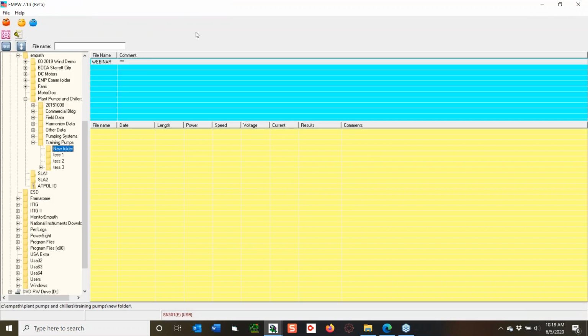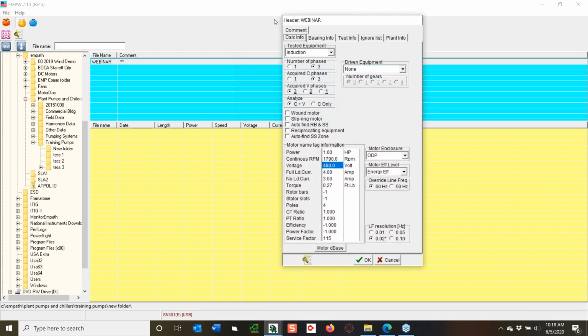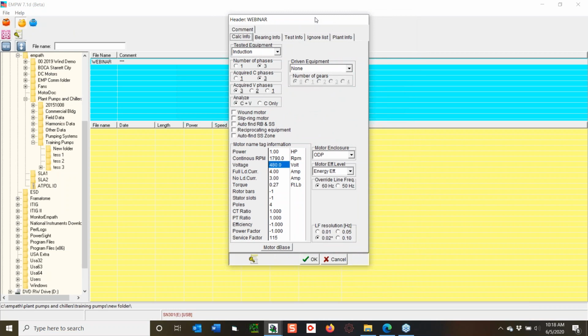So first thing we want to do when I set up the webinar is put in my nameplate. So here we go, nameplate information - you can see I've got certain things here. First thing is it's a VFD application, so we're going to select that. We do have 3 phases of voltage and current, so we're going to set that.